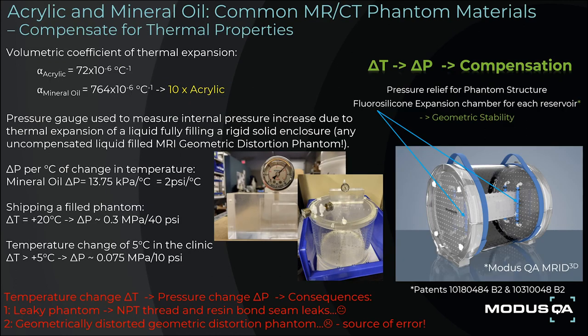Liquid-filled plastic phantom structures in general have a mismatch between the volume coefficient of thermal expansions of the plastic and liquid contrast media. This can be verified by attaching a pressure gauge to measure internal pressure increase due to thermal expansion of a liquid fully filling a rigid plastic enclosure, such as any uncompensated liquid-filled MRI geometric distortion phantom. A 20 degree Celsius increase in temperature in some cases results in an internal phantom pressure of 0.3 MPa or 40 psi. The resulting internal pressure buildup is sufficient to cause deformation of the phantom walls, inducing geometric distortion. This source of error can be mitigated using pressure-compensating expansion chambers designed into the phantom. The fluorosilicone rubber tube expansion chambers function to maintain low pressure within the phantom and divert thermally induced liquid expansion to a flexible elastomer tube while stabilizing the critical plastic structures and fiducial positions, maintaining critical geometric stability of the phantom with temperature increases.